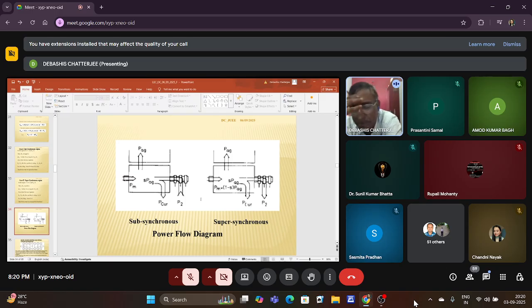Now again you take that example, 1500 RPM 4-pole machine. Now 30% slip, 30% of this speed is actually 450 RPM. So 450 RPM below synchronous speed is around 1050 RPM. Say roughly you can say 1000 RPM. Now 450 RPM above synchronous speed is how much? It is 1950 RPM. Let us say roughly 2000 RPM. So we can have a variation of speed from 1000 RPM to 2000 RPM while generating electrical power, isn't it? So naturally it is shown in this power flow diagram.